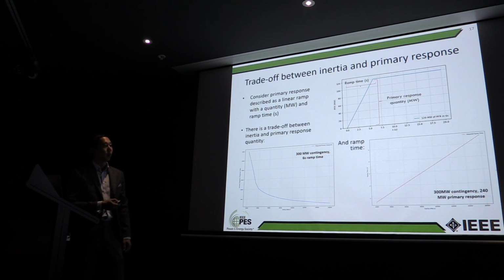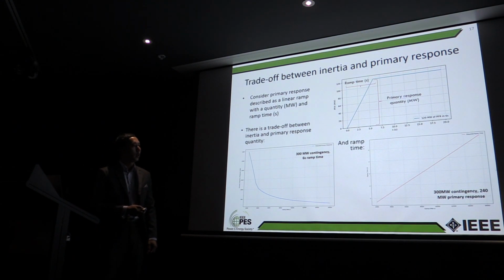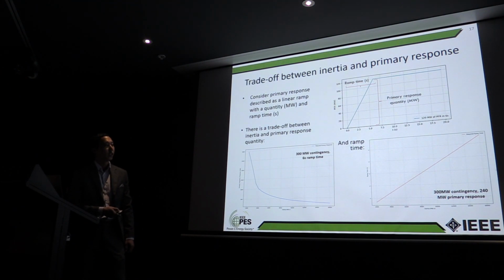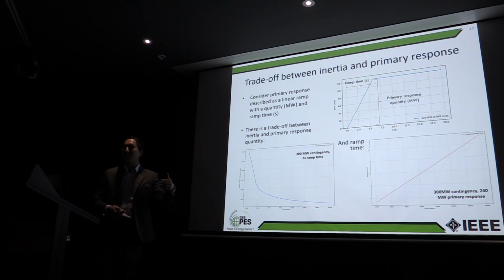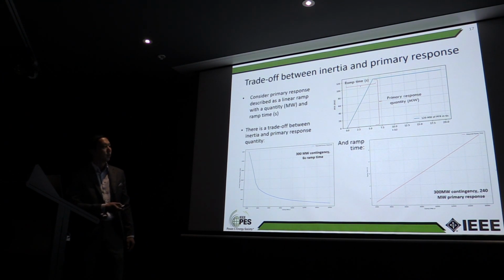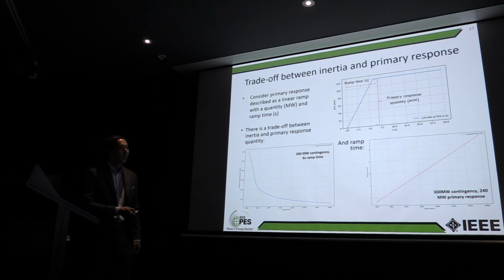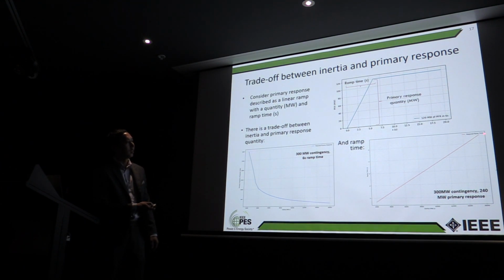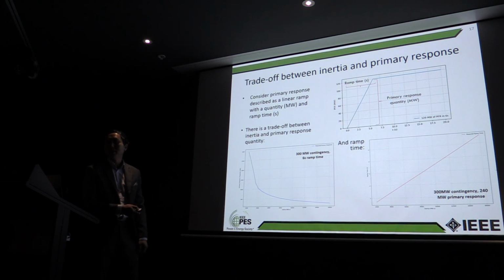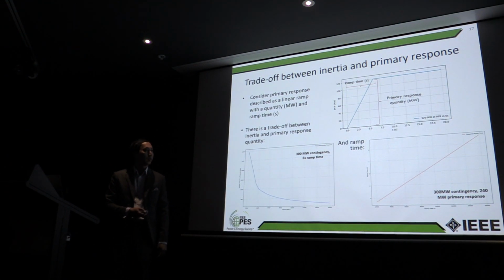The other trade-off is actually ramp time. So if we had just 240 megawatts of quantity, what is the ramp time that we need to keep the frequency above its required level? And what we find is that at very low inertia, you need to ramp up very fast. So here it's less than a second. It's like half a second here. But as you get out to higher inertias, you can have a ramp time here of 5.5, 6 seconds. So that 240 probably corresponds to that value there, actually, at 16,000. So they're the two trade-offs that you have.